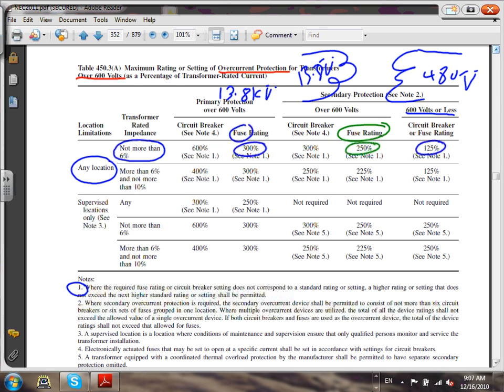I want to bring to your attention note number one right here. I want you guys to read it on your own, but here's what I'm going to summarize. It tells you that if you did all this calculation and you end up with a non-standard fuse or circuit breaker, you go up. Wherever there is a note number one, it means go up. What if you don't have note number one? You have three options: you go sit in the bar, drink and cry; custom design yourself a fuse that's 13.33 amp, for example; or go down, which is what we normally do.